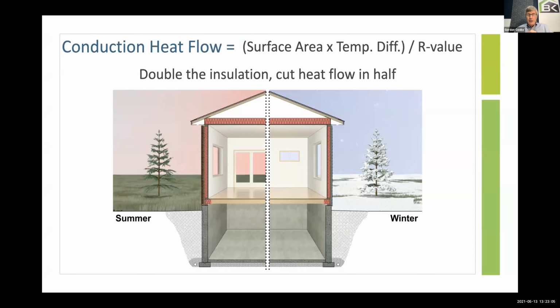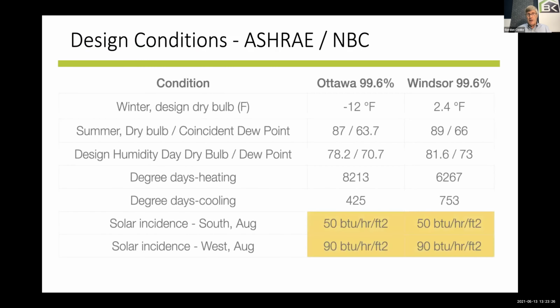And then the next question becomes, Gord, you said surface area times temperature difference. How do we determine what the temperature difference is? Well, that's called design conditions. And you can find these in ASHRAE, and it's actually listed in the National Building Code. The Ontario Building Code references the National Building Code. There's long-term weather data that's been taken, and they're basically 30-year averages. And if you'll notice there on the right, I've shown 2 different cities. I didn't go outside of Ontario, sorry for that.